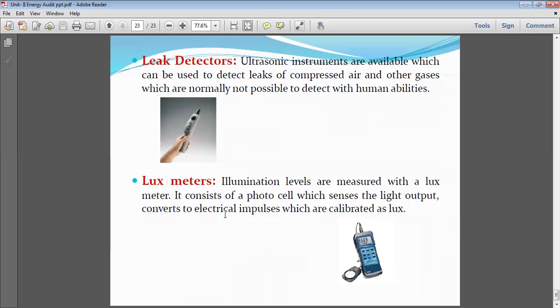By trapping these leakages we can conserve energy. For example, if compressed air is leaking, the compressor runs continuously with no downtime. If you fix the leakages, the compressor will shut off for certain periods and restart only when pressure drops — increasing the stop time and conserving energy. Leakages may be water leakage, cold water leakage, leakages due to thermal insulation failure, or pipeline leakages. By addressing all leakages we can achieve remarkable energy conservation.